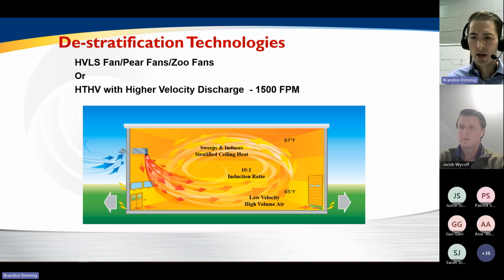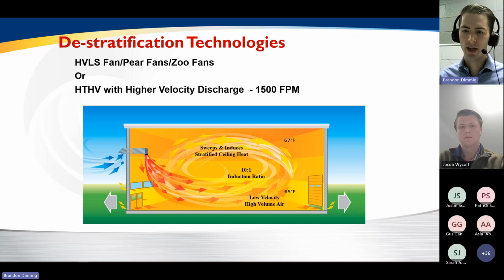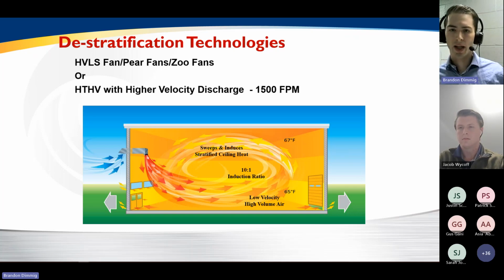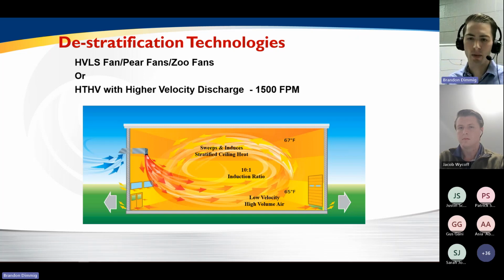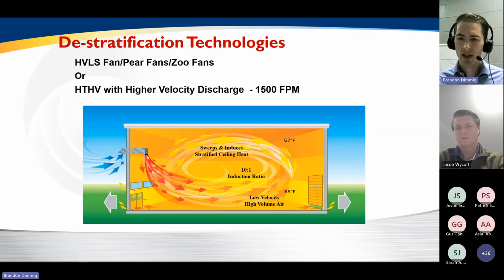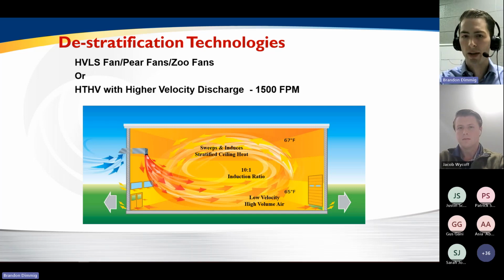There's an induction effect that occurs when you're moving air at a high velocity. And in the case of an HTHV unit, for every 1 CFM of discharge air, you end up moving about 10 CFM of building air. And so you can get a lot of movement in a high-bay space and destratify it really well without adding any additional equipment to do that. So again, not only are you heating the space really efficiently, but now you have a really great system effect that allows you to destratify it and keep temperatures even, not only horizontally, but also vertically, without having to add other equipment and integrate and install it.